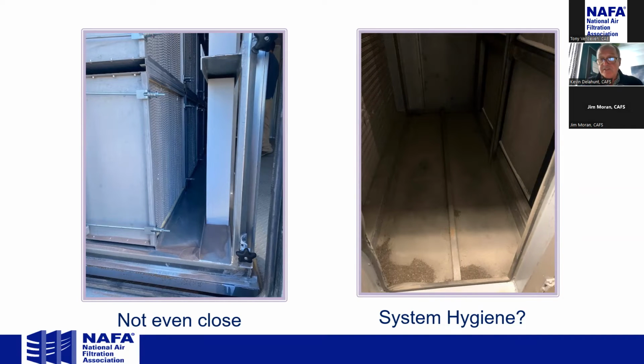And system hygiene is just the cleanliness of the filter bank in itself, the coil, and that when you see in this case on the right-hand side, you could probably take a broom and a dustpan in there and clean up the dirt or a vacuum. But this is downstream of the filter. The filter's on the right-hand side if you're looking at the picture, and would indicate that there is bypass in that system, either around the filter or through the filter. So it needs to be identified and rectified.